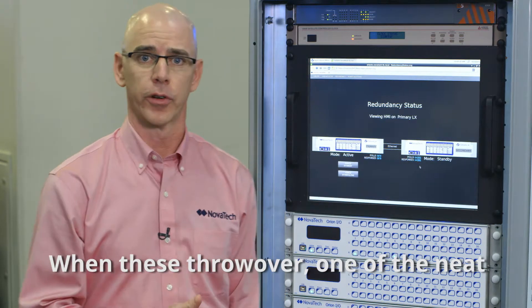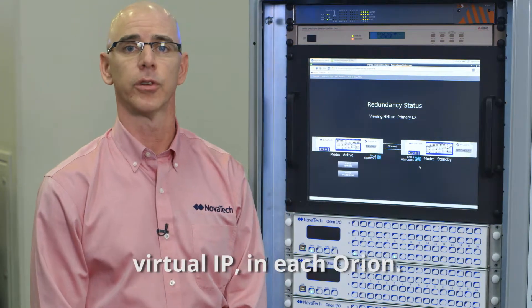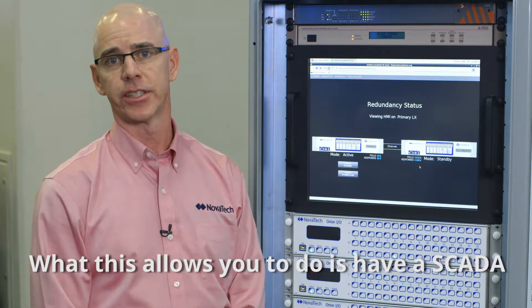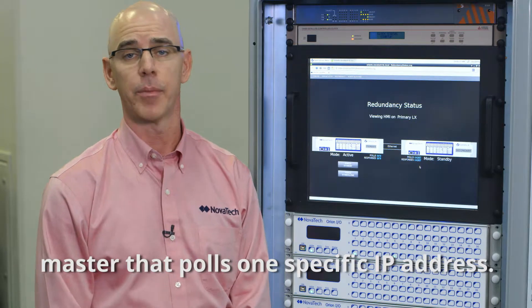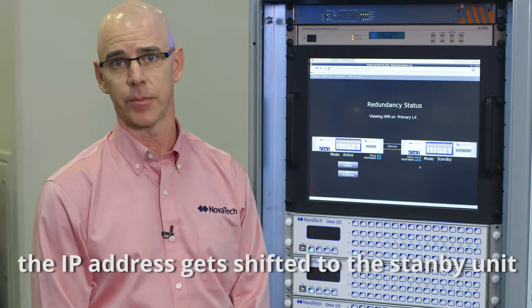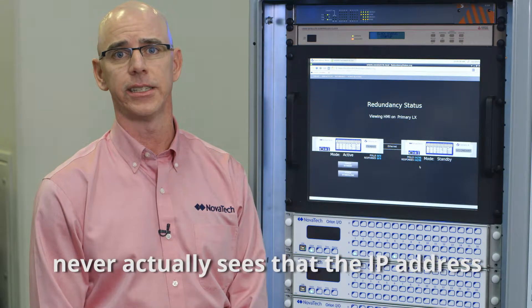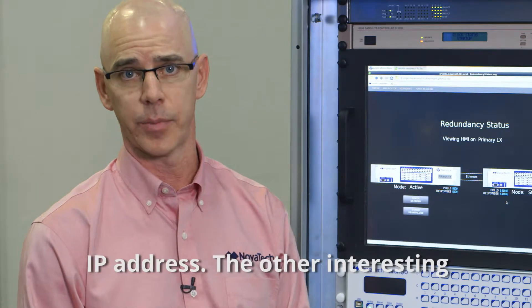When these throw over, one of the neat features is we have the ability to create a virtual IP in each Orion. What this allows you to do is have a SCADA master that polls one specific IP address. And then when the Orions throw over, the IP address gets shifted to the standby unit that is now active, and your SCADA master never actually sees that IP address change — it's always polling one single IP address.